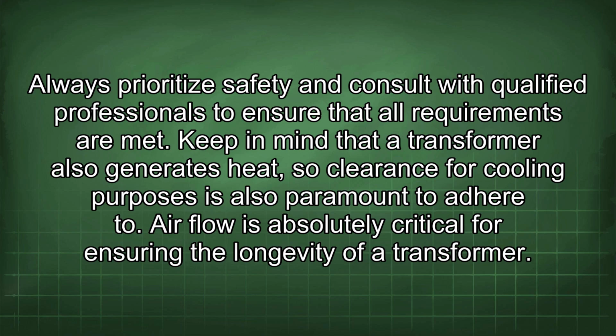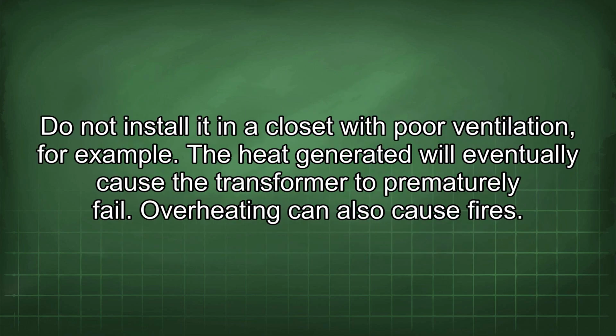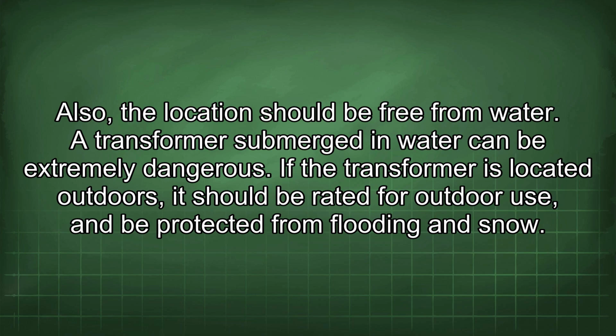Keep in mind that a transformer also generates heat, so clearance for cooling purposes is also paramount to adhere to. Airflow is absolutely critical for ensuring the longevity of a transformer. Do not install it in a closet with poor ventilation, for example. The heat generated will eventually cause the transformer to prematurely fail. Overheating can also cause fires. Also, the location should be free from water. A transformer submerged in water can be extremely dangerous.